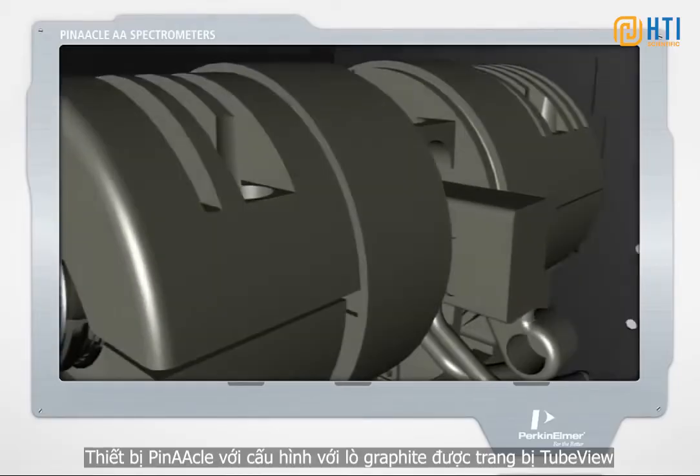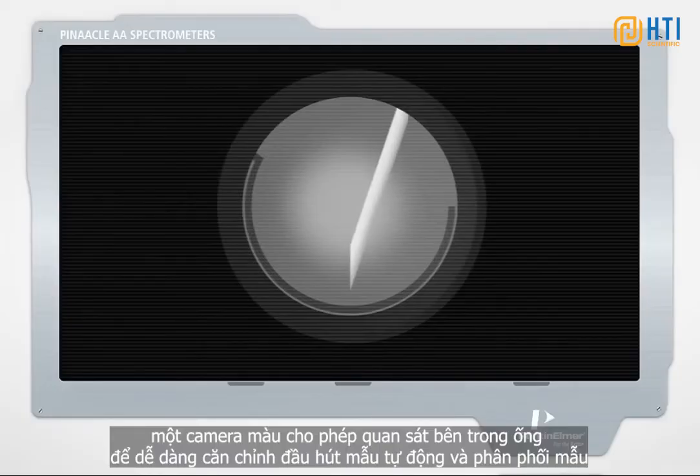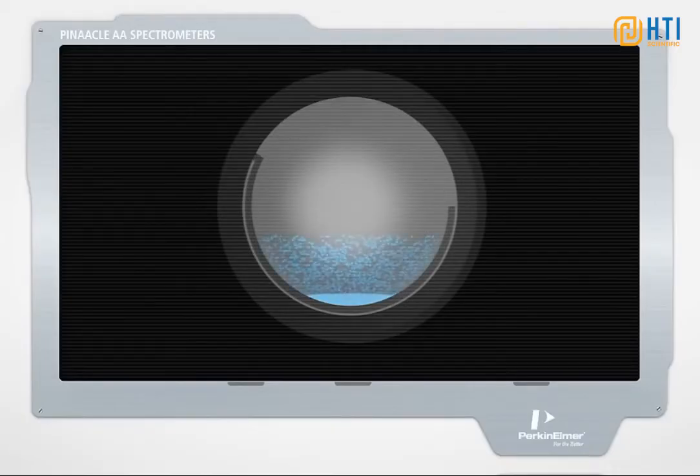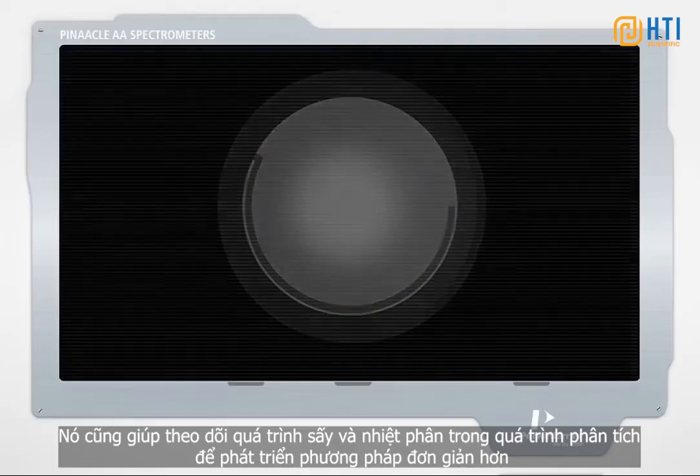PinAAcle instruments are configured with a graphite furnace equipped with TubeView, a color furnace camera that allows you to view inside the tube for easy auto-sampler tip alignment and sample dispensing, and to monitor drying and pyrolysis during analysis for simpler method development.